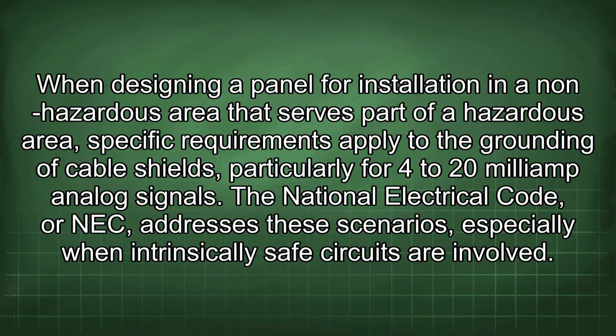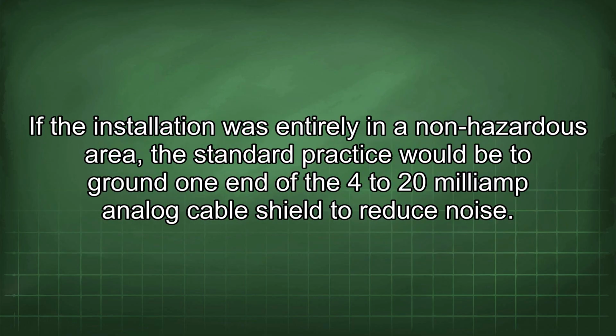When designing a panel for installation in a non-hazardous area that serves part of a hazardous area, specific requirements apply to the grounding of cable shields, particularly for 4 to 20 mA analog signals. The National Electrical Code, or NEC, addresses these scenarios, especially when intrinsically safe circuits are involved. If the installation was entirely in a non-hazardous area, the standard practice would be to ground one end of the 4 to 20 mA analog cable shield to reduce noise.